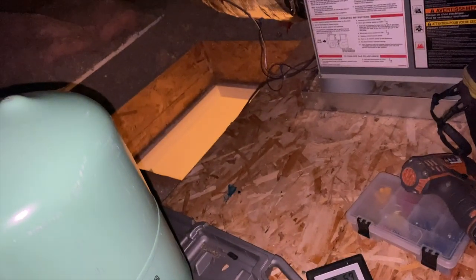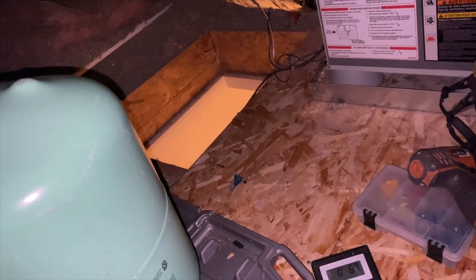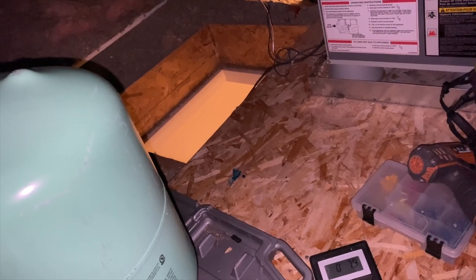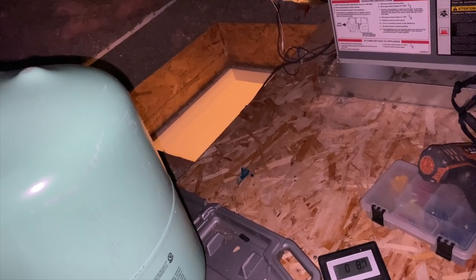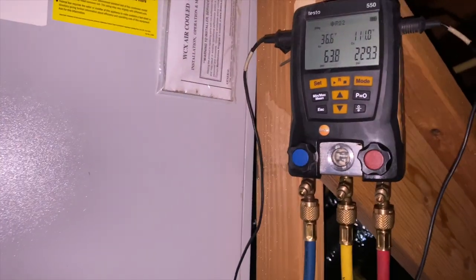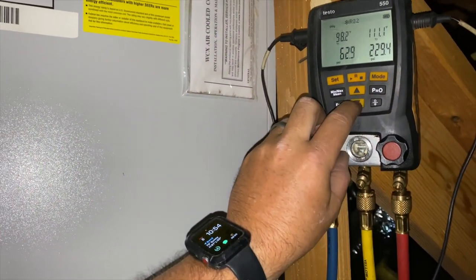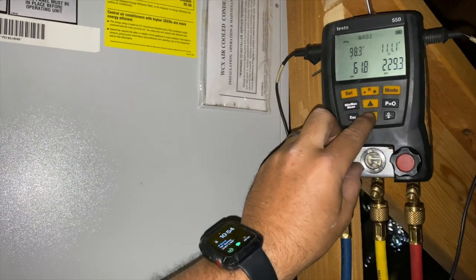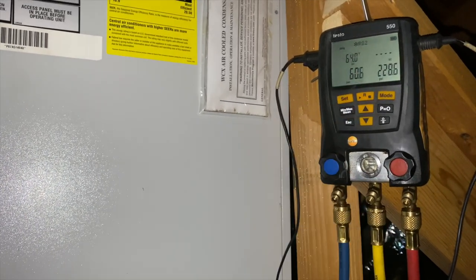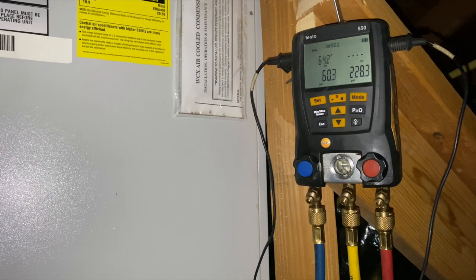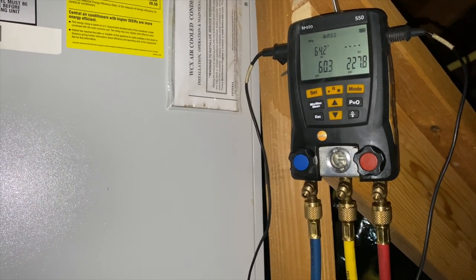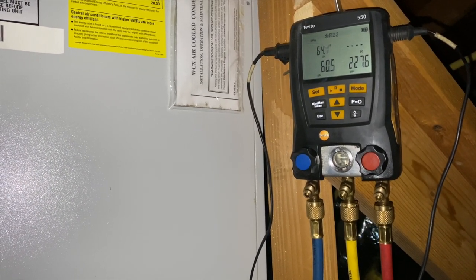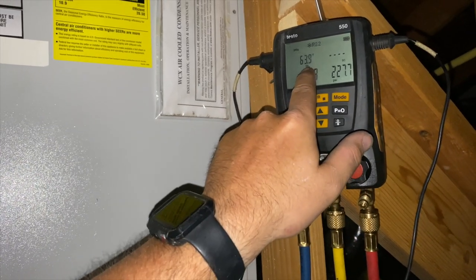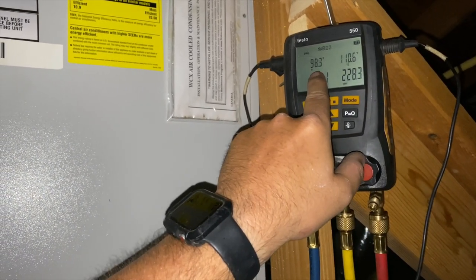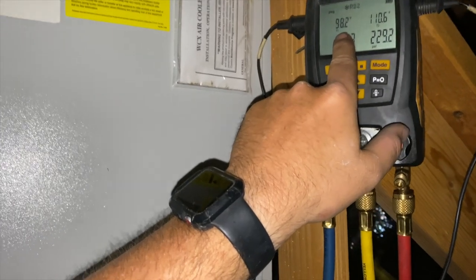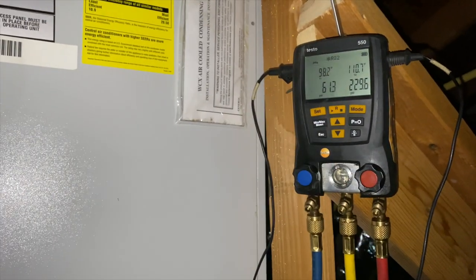So we're at 5 ounces, 6 ounces, 7, and 8 ounces. Now we're just going to let it stabilize, and hopefully our suction temperature comes down and we get a better superheat too. When you want to reduce your superheat, you add refrigerant. To increase it, you remove refrigerant. It is starting to come down a little bit. Our temperature here is starting to come down a bit. So we're going to let it sit for a minute and see what it does.